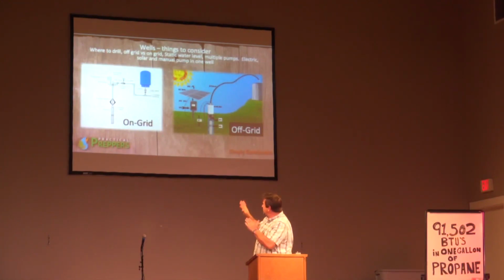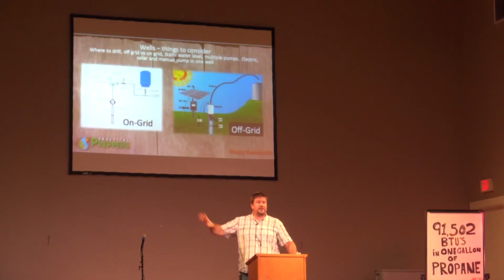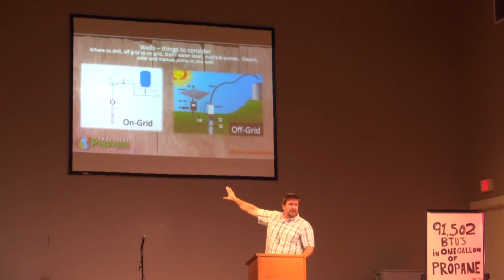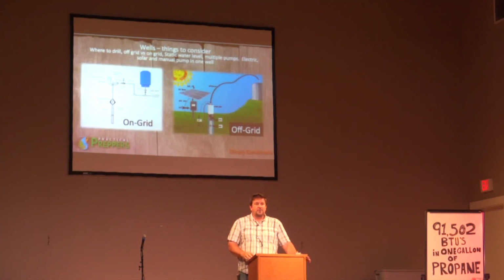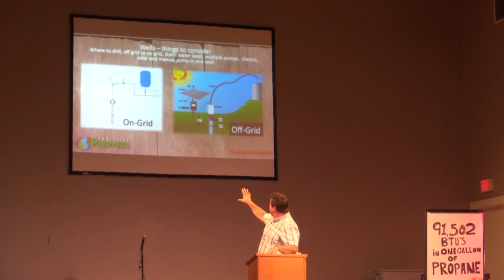There's a lot of things we can do with that system. The cool thing is, because we have a 6-inch casing, we can leave that system alone. It's not broke, don't fix it. You can put a lot of things in parallel with what's already in the well. You can stack 3 or 4 pumps in that well at different heights, leave the original alone, and add a new pump.